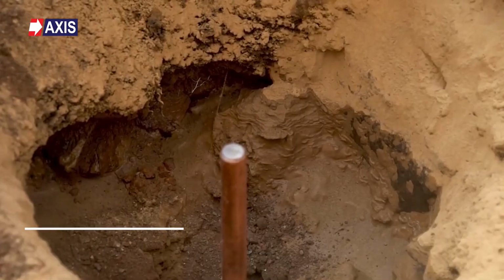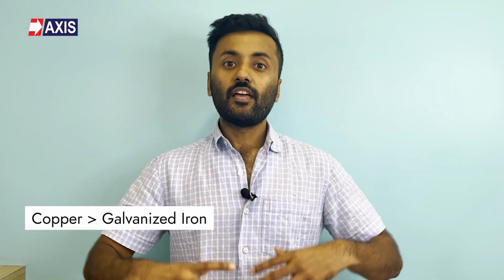Finally, the use of copper bonded rods in maintenance-free earthing. Copper bonded rods are better than traditional pipe earthing for several reasons. First of all, copper is more conductive than just GI. Secondly, they are more durable and resistant to corrosion than pipes.